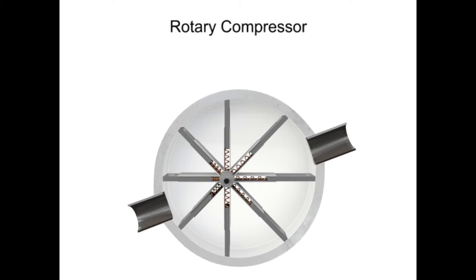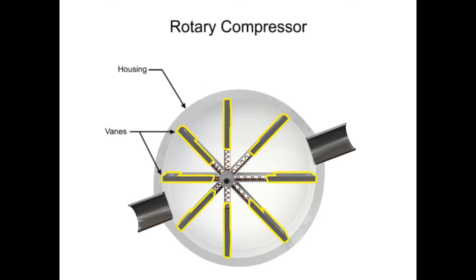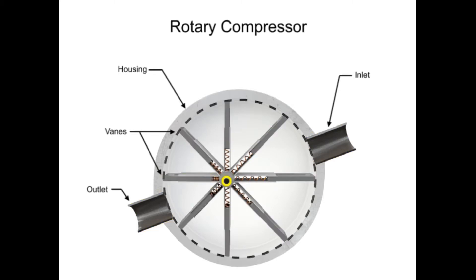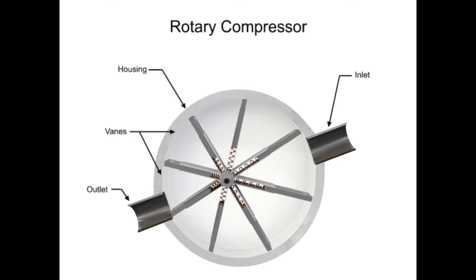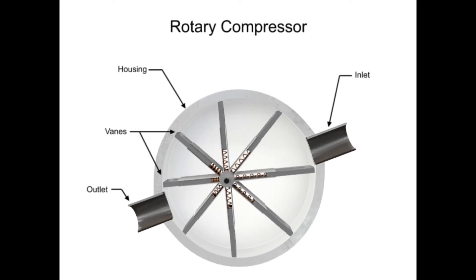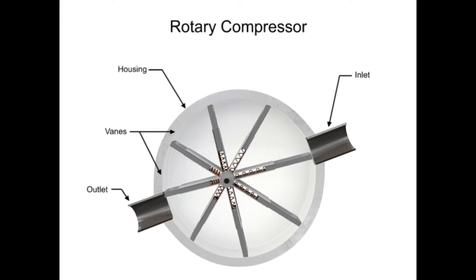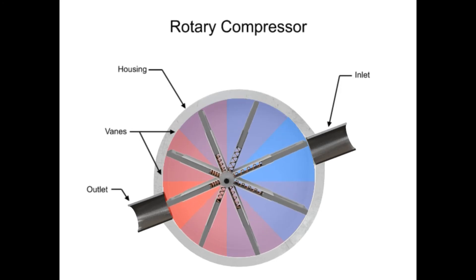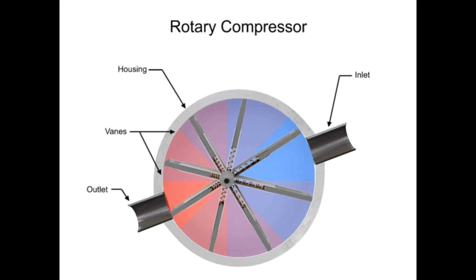Rotary compressors typically consist of a cylindrical housing with adjustable rotary vanes, an inlet, and an outlet. The vanes are on an off-center drive shaft. As the shaft rotates, the vanes slide in and out to maintain contact with a cylindrical compressor wall. As they do, they create chambers within the cylinder of varying sizes.